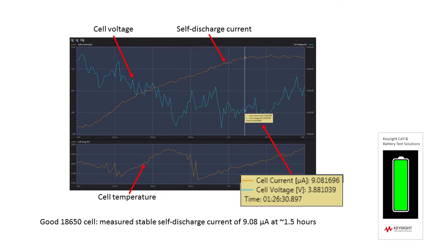Results obtained with an off-the-shelf self-discharge measurement system indicates that for smaller cells, like cylindrical 18650 or 2170 cells, you can determine the stable value of the self-discharge current in as little as 30 minutes to 2 hours, depending on the cell characteristics.